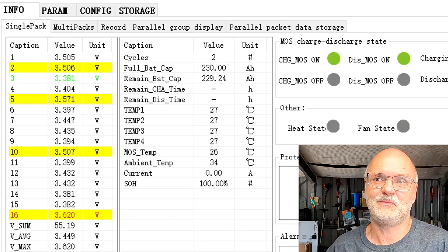So if we go back into the live view now, we're at 55.2 volts absorption voltage. You can see cell number 16 is at 3.62 volts, but there's no alarm, because the alarm is set to 3.7. So we wouldn't even get an alarm. There's no alarm, no protection, nothing. It's just sitting there balancing, but no alarm whatsoever.